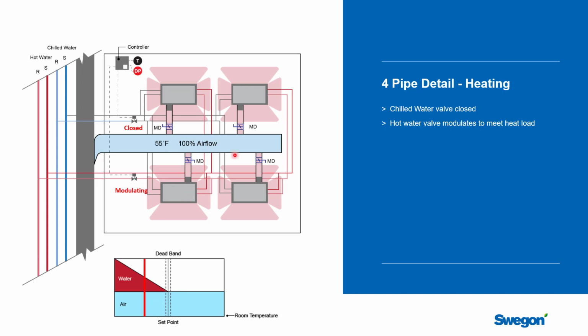And then if the space temperature continues to drop because there's heat loss through an exterior exposure or something, then what we would do is continue to add more hot water to it. This supply air temperature would start to go up above the room temperature, typically not more than about 10 degrees Celsius or 15 degrees Fahrenheit. Otherwise, we start to get buoyancy issues and stratification issues. But we can add that heat into the space and meet the load.